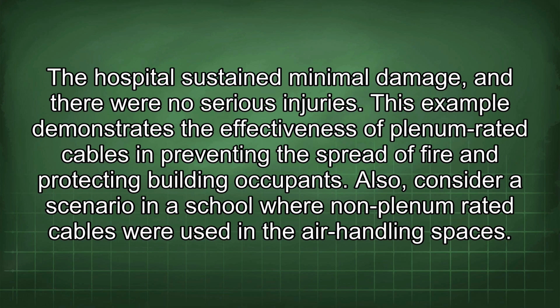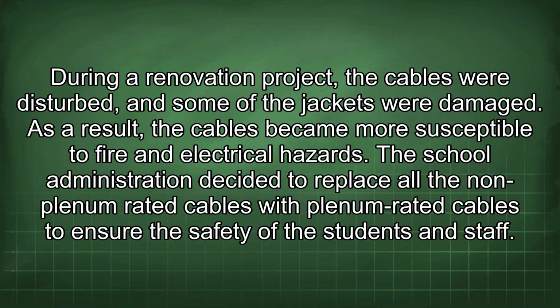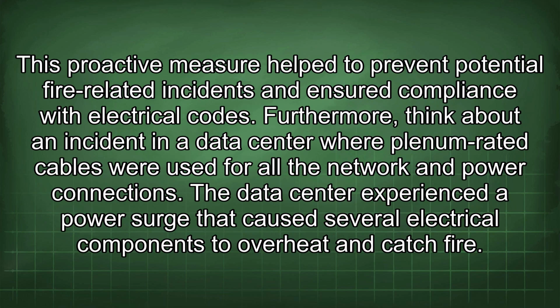Also, consider a scenario in a school where non-plenum rated cables were used in the air handling spaces. During a renovation project, the cables were disturbed and some of the jackets were damaged. As a result, the cables became more susceptible to fire and electrical hazards. The school administration decided to replace all the non-plenum rated cables with plenum rated cables to ensure the safety of the students and staff. This proactive measure helped to prevent potential fire-related incidents and ensured compliance with electrical codes.